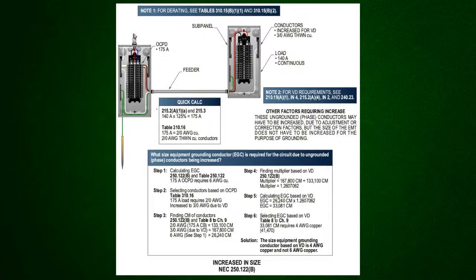26,240 circular mil. So now what I need to do is get a multiplier to put onto that number 6 that has 26,240 circular mil. And the way I get that multiplier is taking that 3/0 conductor, which was 167,800 circular mil, and dividing the 2/0 into it, which is 133,100 circular mil, and that's going to give you 1.26076. Okay, so you're just going to... sounds about like a 2/0 to me. No, I'm just kidding. Yeah. So you just take that and you put it onto that 26,240 circular mil, and that's going to give you 33,081 circular mil. Then you look over and find the circular mil that's above that, and it's going to tell you that you have to increase it at least one more size to a number 4 equipment grounding conductor due to your voltage drop or correction or adjustment factors.